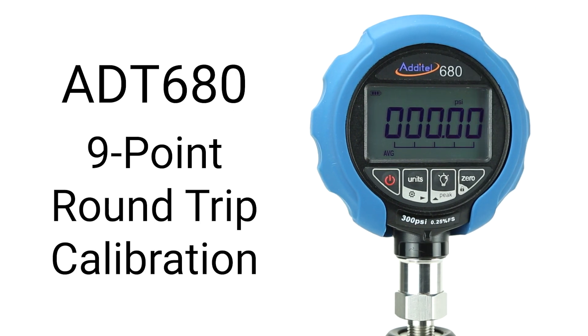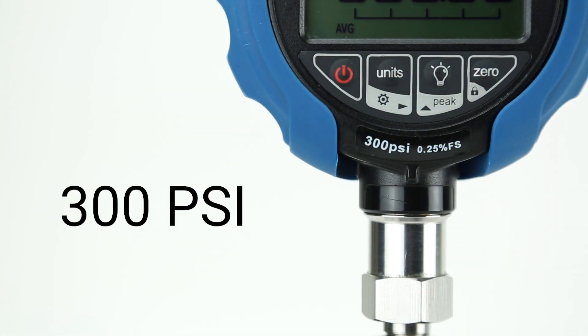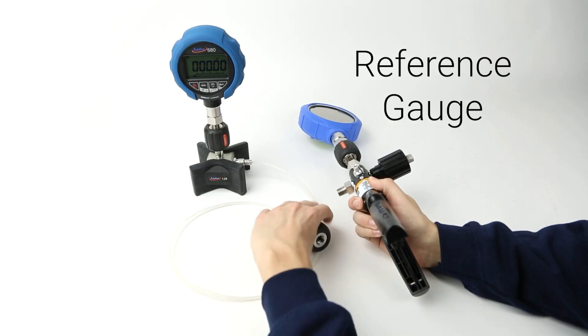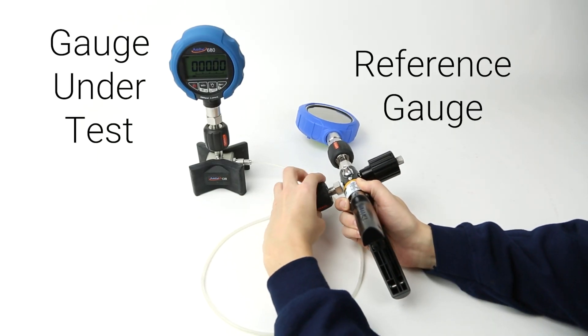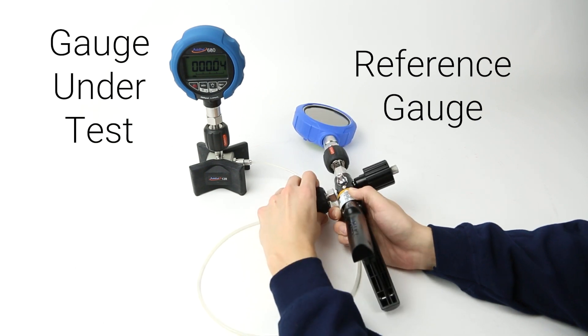The device under test for the calibrations will be an Additel 680 digital pressure gauge with a range from 0 to 300 psi or 20 bar. For the first calibration, we'll connect the hand pump and reference gauge to a manifold with the gauge under test using Additel quick connectors.